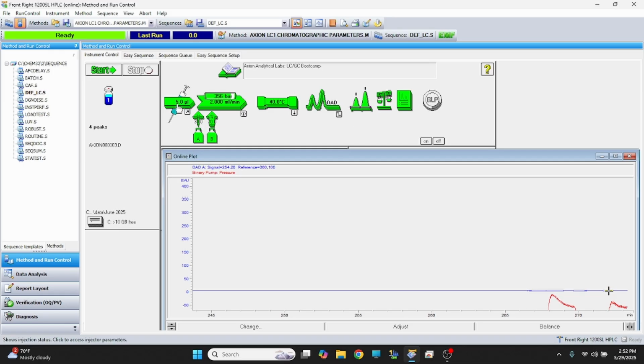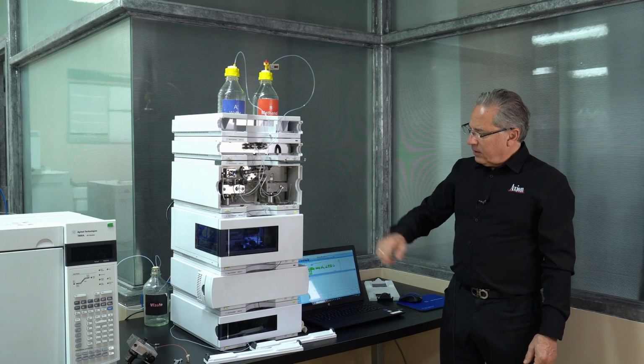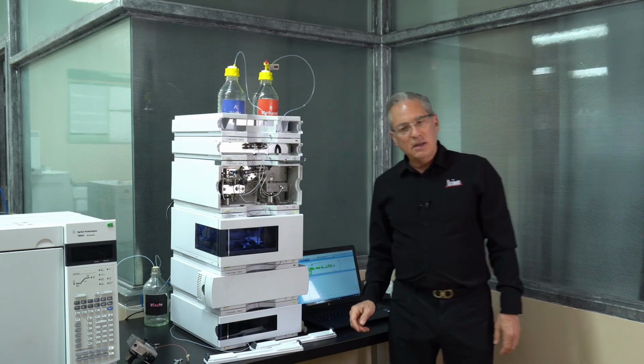That means I got my autosampler, my pump, my column compartment, my detector. Everything is green, which means they're all ready to go. If I click the start button, what it's going to do, it's going to tell the autosampler to do its thing. So first, it's going to balance or zero the detector. Once it does that, it's going to tell the autosampler to do its little song and dance.